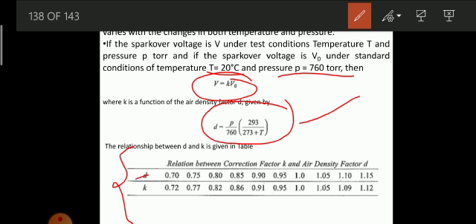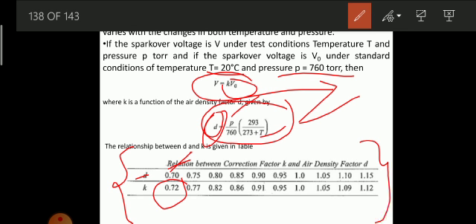If D is equal to 0.70, see, when we are calculating D, because we know the current pressure and the current temperature, you have to calculate D. Whatever D value you get, that value of K you have to apply in this equation. So this is the table giving you the relationship between the correction factor K and the air density factor D.